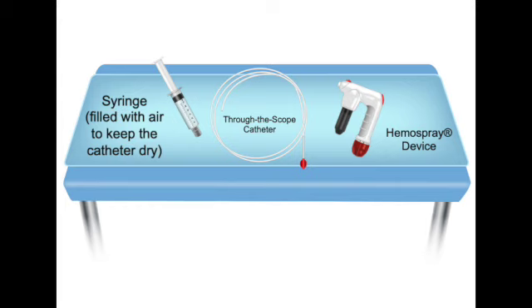You have to keep pushing air through it. So like creating a constant internal breeze blowing outwards. Exactly. Actively blowing any potential moisture back out the way it came. And that flushing can't stop, not even for a second while they're advancing it. So you've got the endoscopist steering the scope and pushing the catheter, and someone else, an assistant maybe, constantly pushing the air syringe plunger, all while remembering the catheter itself is apparently quite delicate.